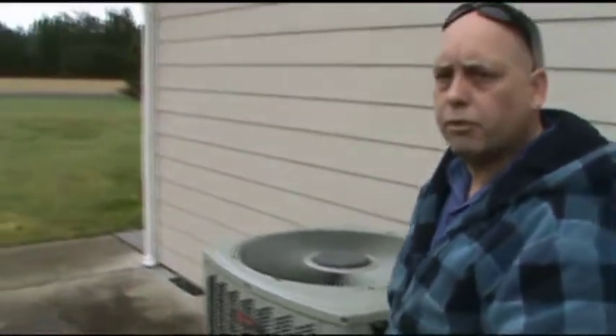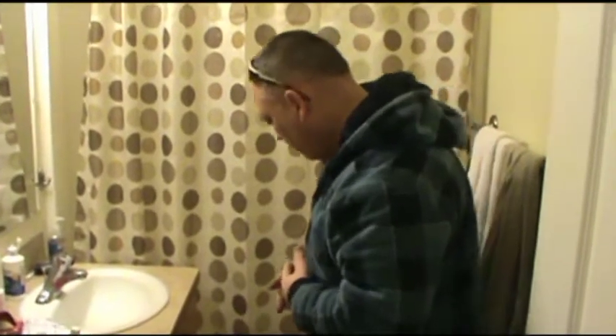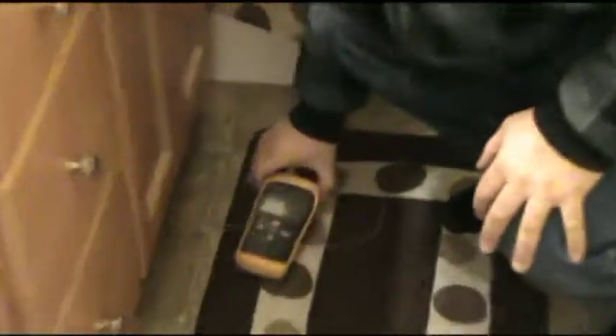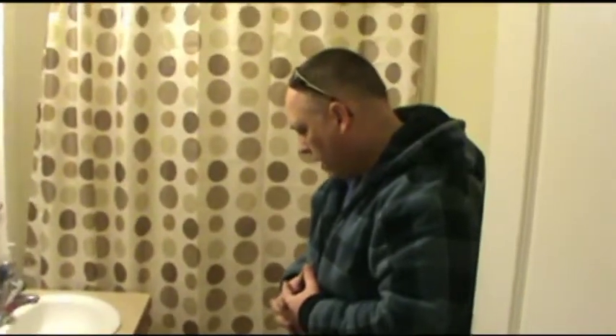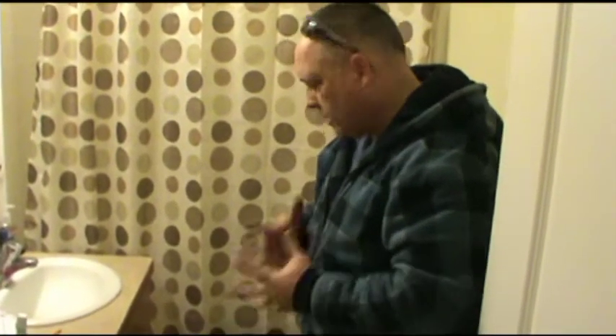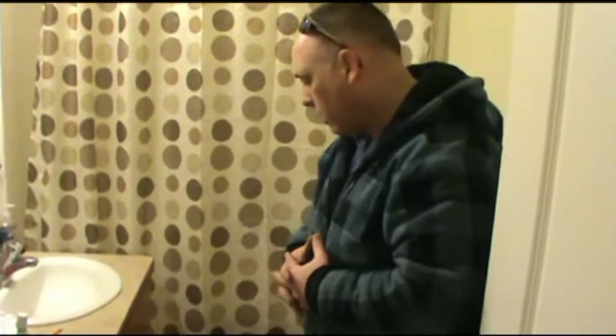Let's go inside and we'll check the temperature coming out of the ductwork. Typically, we want to see about a 20 degree temperature difference when we're running in cooling. We knew from a few minutes ago that our return air temperature was 71. And right now, we're getting somewhere around 55, 56 degree air coming out of the ductwork. Now the ductwork is still hot from running in heating for 10 or 15 minutes there, and I don't want to run the machine too long in the cooling mode like this. But I've got about a 17 degree split already. So I know I'm good in the cooling mode.